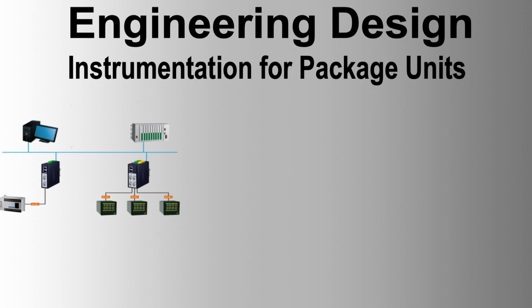The contractor shall ensure that the equipment package vendor details the hardware and software requirements with the DCS vendor to enable intersystem communication. All signals generated from the equipment package control system and IPS logic solver shall be available for transmission to the plant DCS within 1 second. The vendor shall indicate the refresh rate of analog signals in his system.